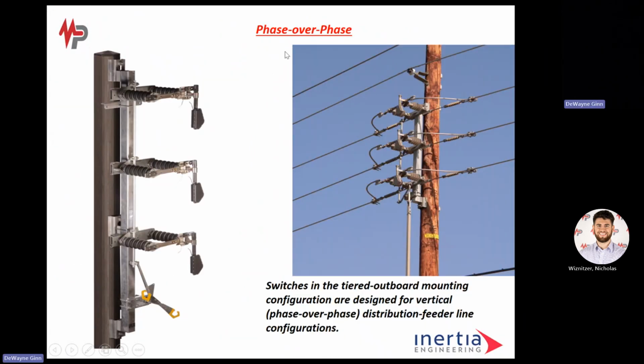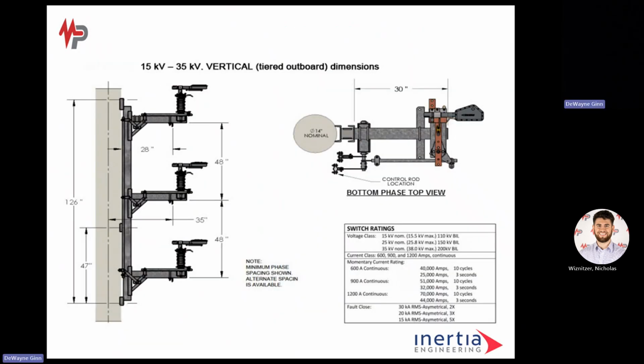Phase over phase. If you look at this configuration, on the left-hand side, again, you have a hook stick operator. It looks like a pole going down. That's a down rod for a mechanical or manual operating to open and close the switch. You could also have a motor operator on that. These switches, the blade drops down from the bottom and back up to open and close. This is called a tiered outboard. Again, it's a phase over phase. If you notice, the switches are sitting upright, so they would open in a horizontal position, the blades.